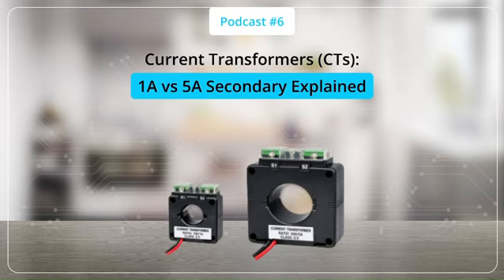Now, a common question. Can you replace a 5A CT with a 1A CT? The answer depends on system compatibility. You need to ensure that the relays and instruments can accept a 1A input. While many modern systems support this, some older systems may not. If replacement is possible, adjustments may be required in system settings. However, if the system is strictly designed for 5A, hardware limitations may prevent such changes. It is always important to test the system before making any replacement to avoid incorrect readings or unwanted trips.